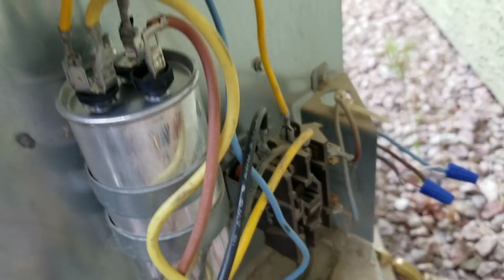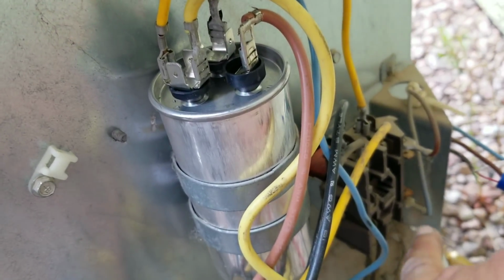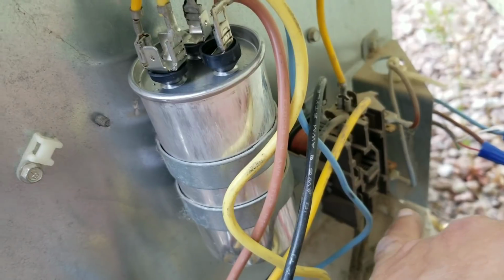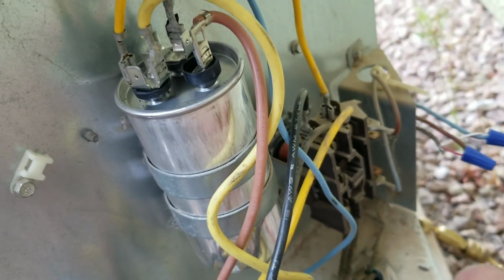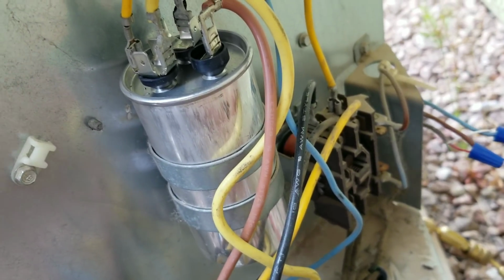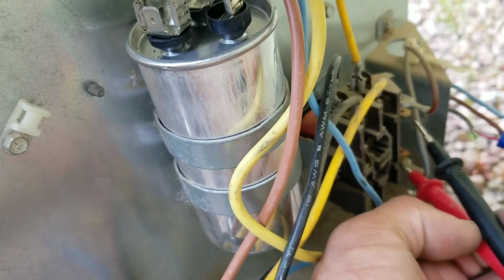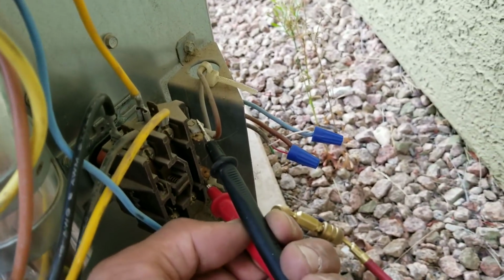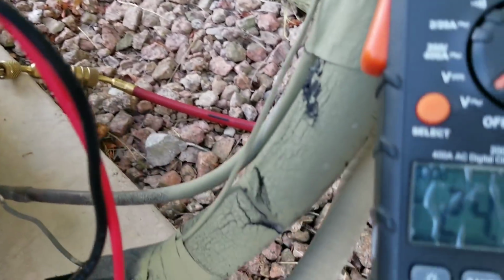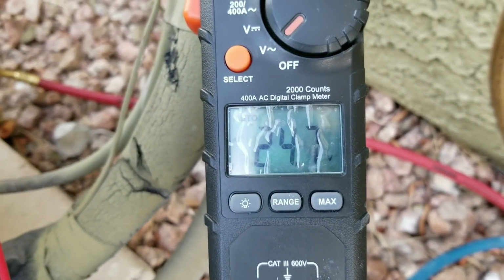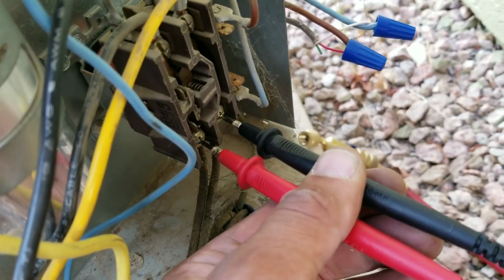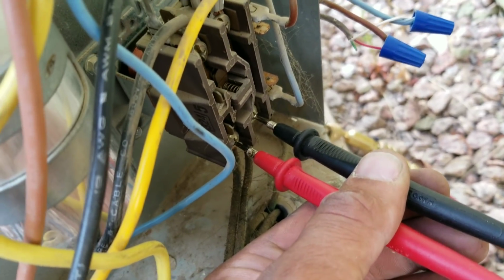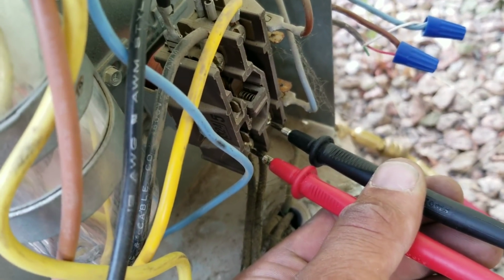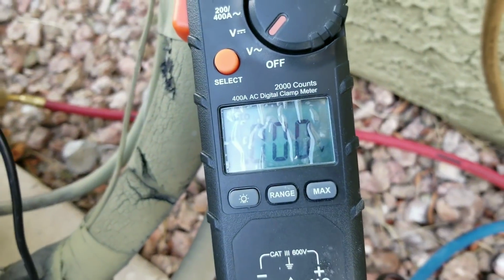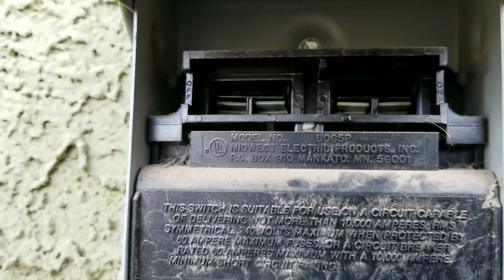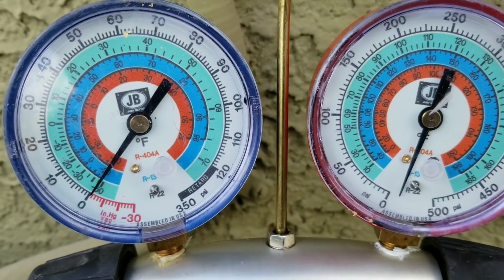Right now I do have my contactor engaged because my thermostat is calling for cool. The thermostat is set to auto cool. I put the temperature down to 75. You could take your low voltage reading, and you can see here that I do have 24 volts. Obviously, we're taking a reading for the voltage coming from my disconnect, and I do not have any voltage because I removed the disconnect. I'm going to reattach my gauges.